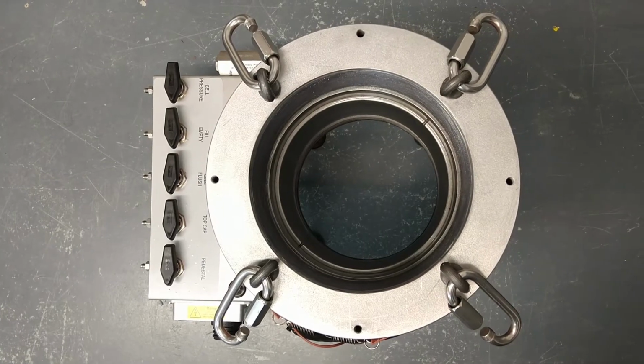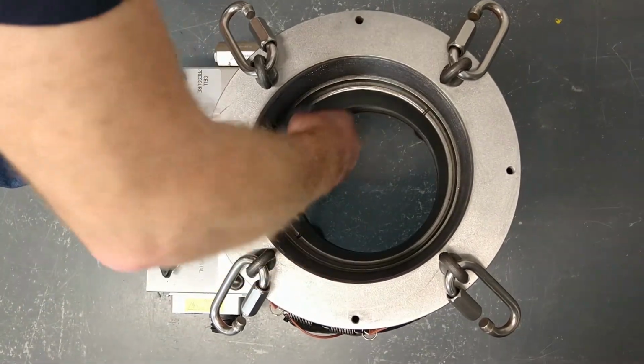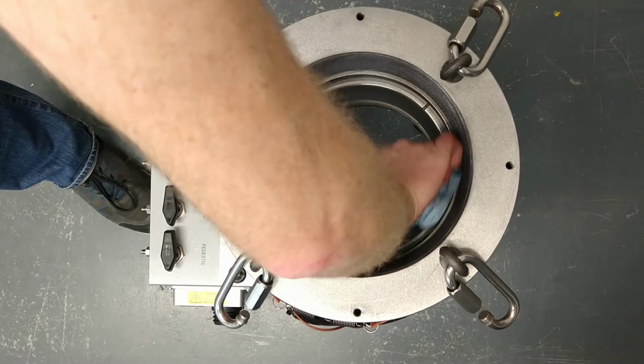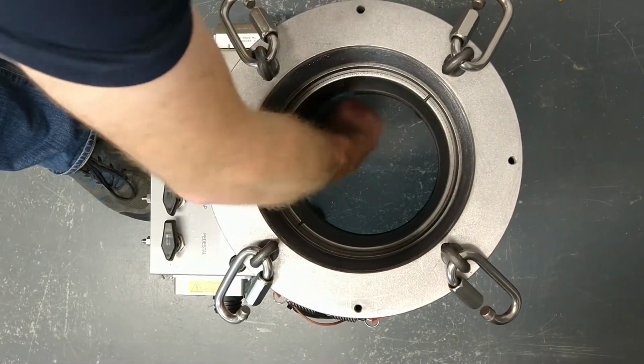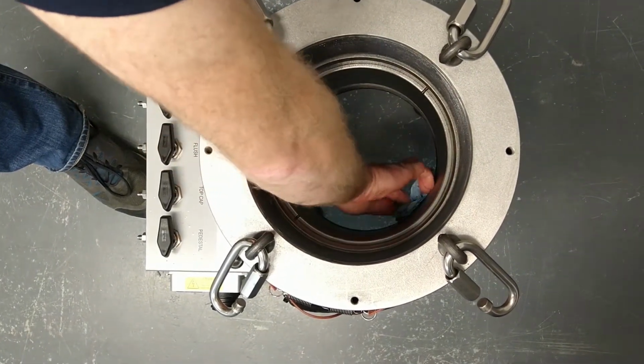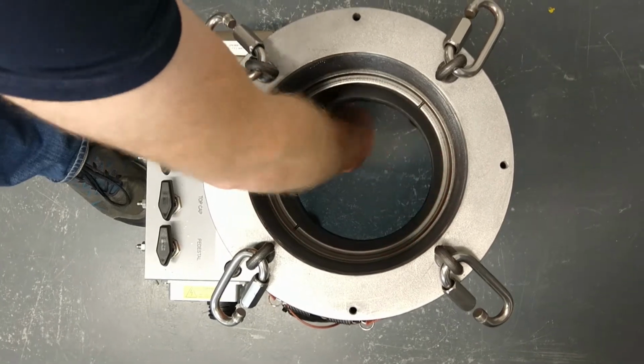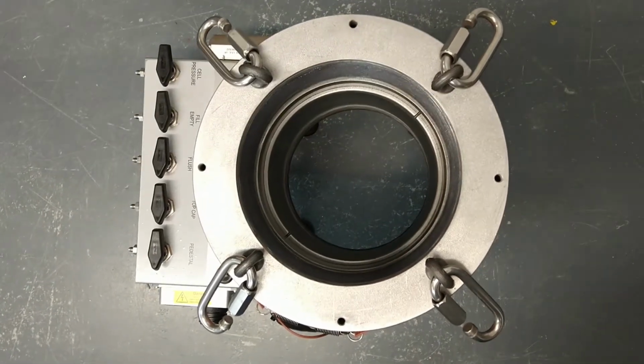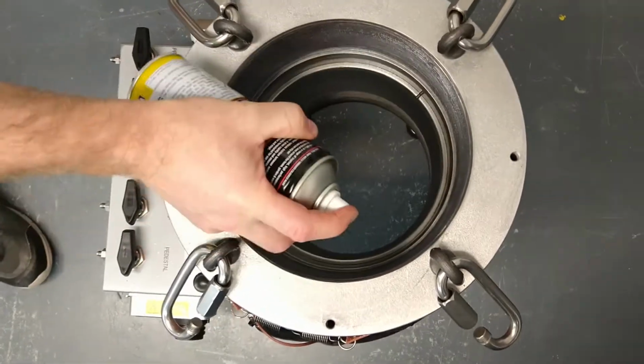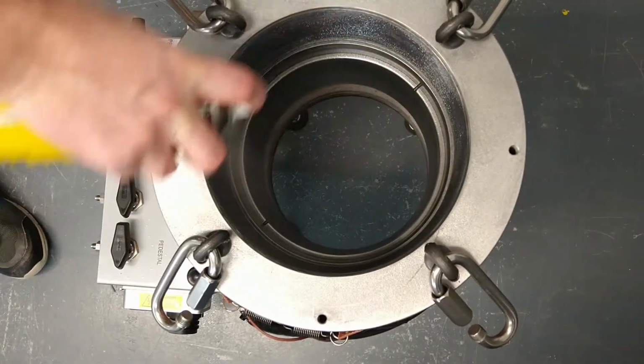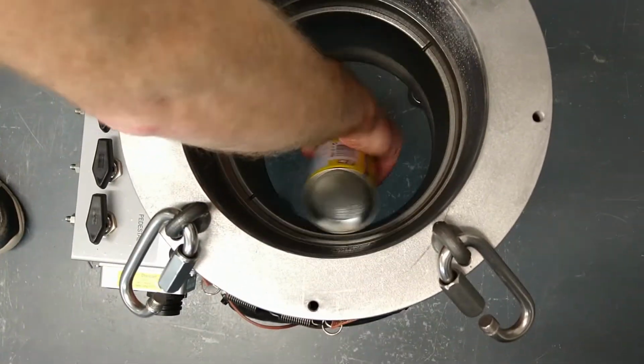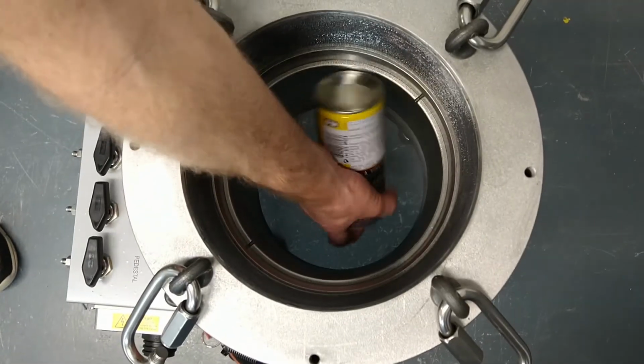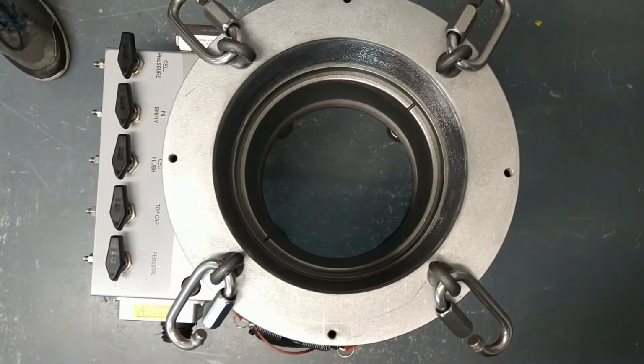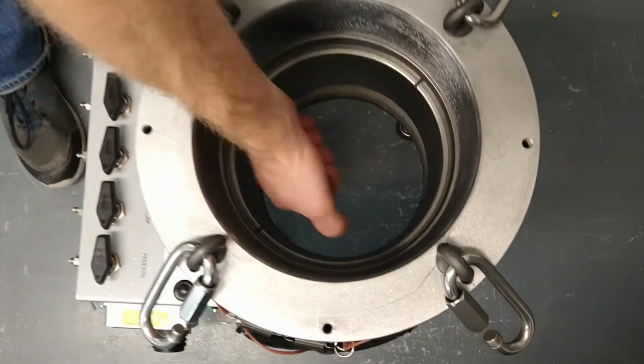The cell base and cell top will have a molybdenum grease applied. This should be topped up when necessary to avoid seizure of the threads. Clean the sealing faces located inside the cell wall. Use a silicone spray to lubricate the threads inside the cell wall. Apply a layer of silicone grease to the upper and lower sealing faces, making sure to cover the chamfered edge.